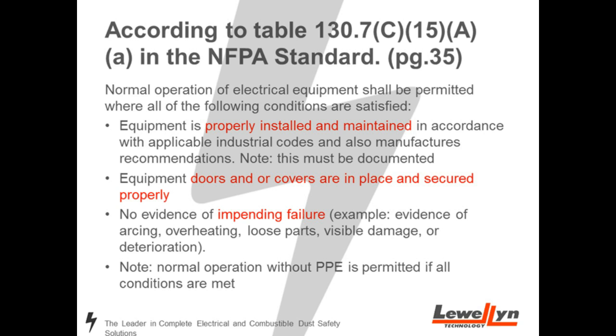I always use this example: I have a pickup truck with evidence of impending failure - it's got rust, parts and pieces falling off of it. That would be a sign of impending failure. Same with doors and covers - rusted off, hinges broke, screws missing, knockouts missing - all things that would not satisfy these three items, meaning you'd have to wear the appropriate PPE. But as long as you can verify your disconnects are covered under these three requirements, you can now operate them without wearing the level of PPE that might be on the arc flash label.